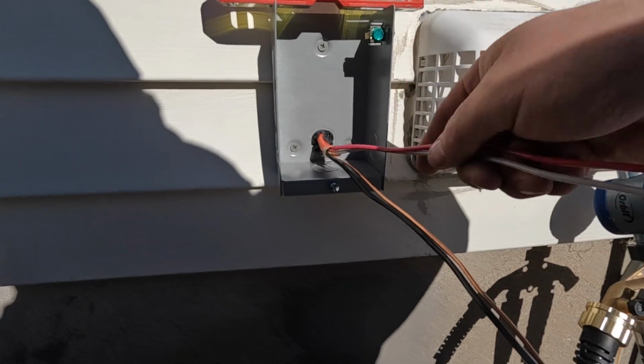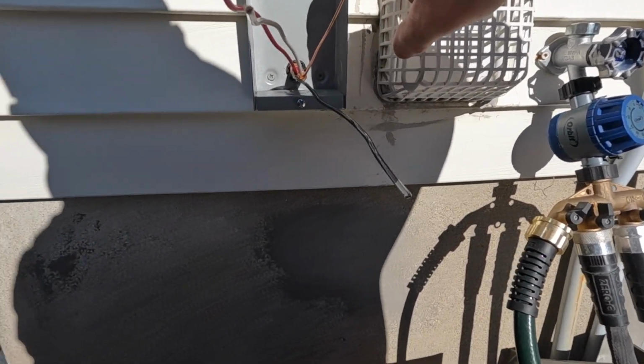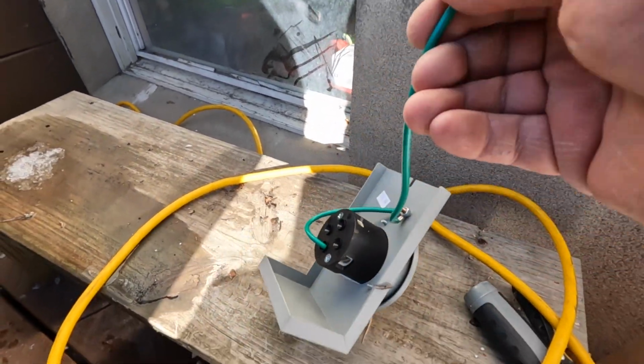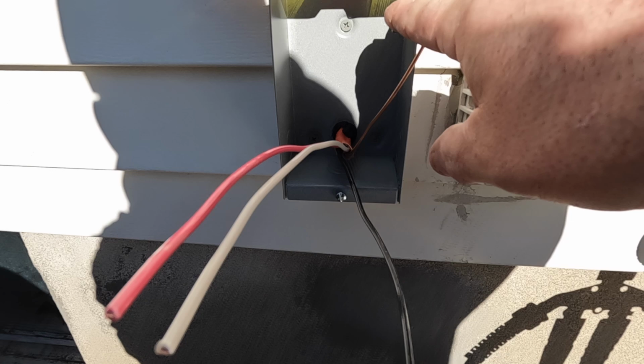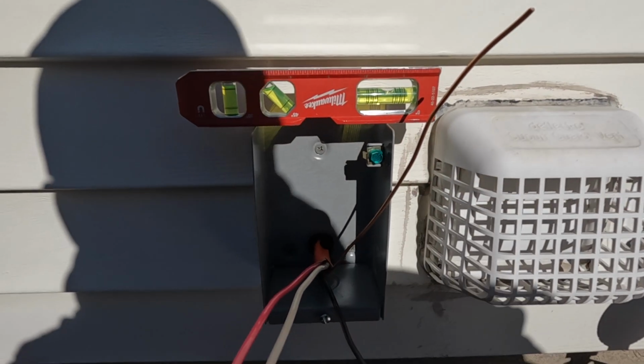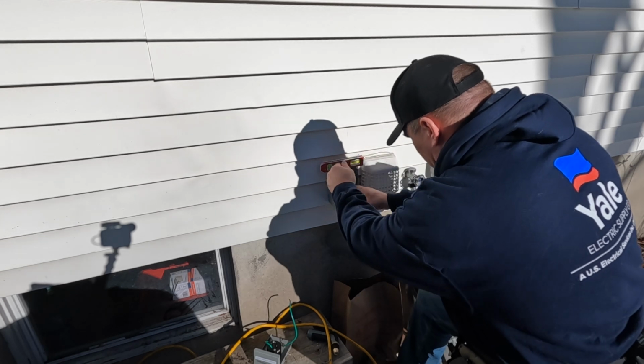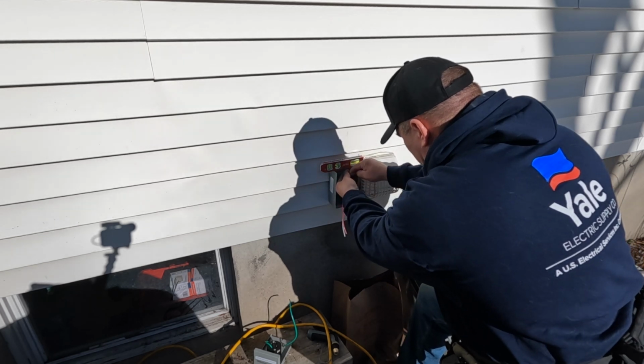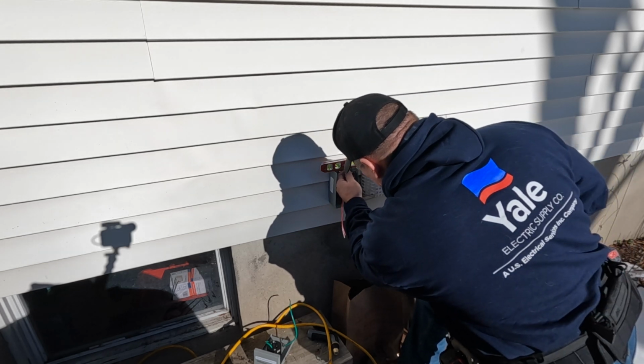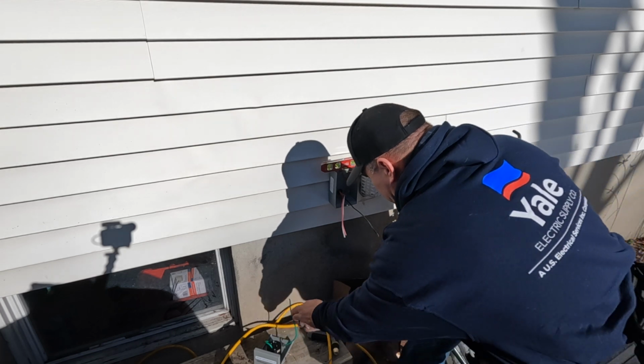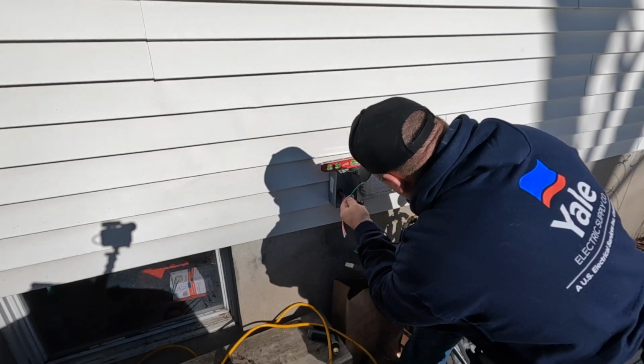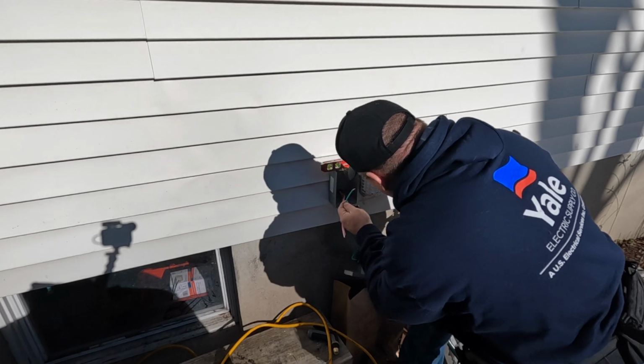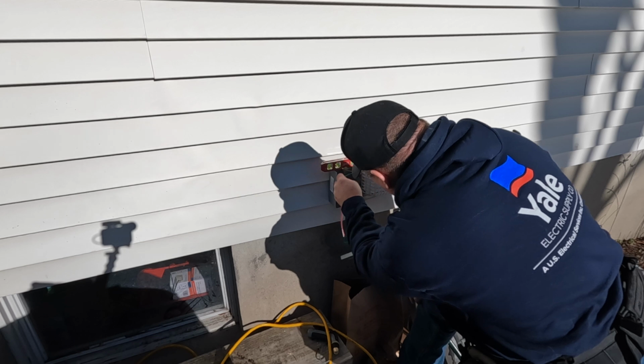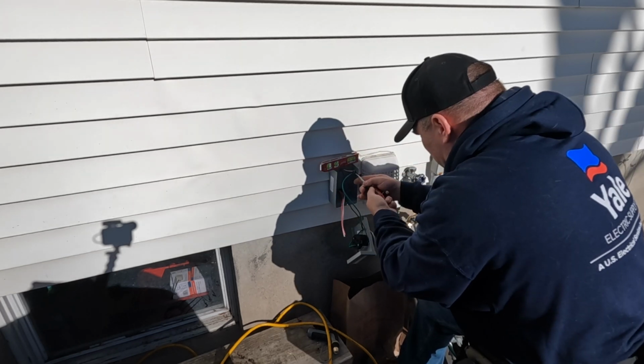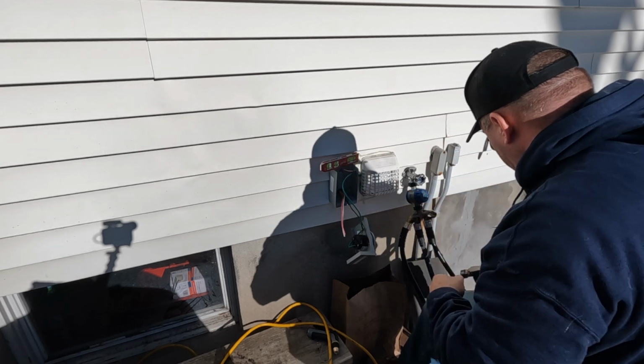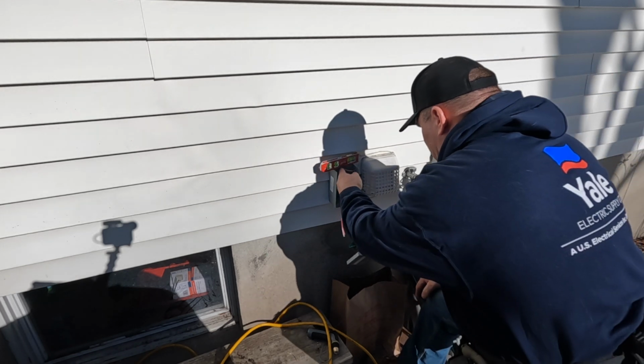What we're doing now is we're going to attach the equipment grounding conductor to this lug, and then we're going to take the equipment grounding conductor from the inlet and attach it underneath this lug as designed by the manufacturer. That's the way we are going to do it. All right, so I'm going to tuck this all the way in the back and out of the way. I'm going to go underneath the terminal strip. It's almost like a circuit breaker, like the QO breakers that you can put 2 circuits underneath. All right. Now our equipment grounding conductors are all set up.